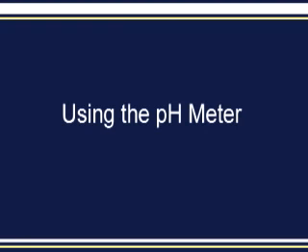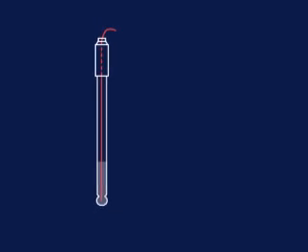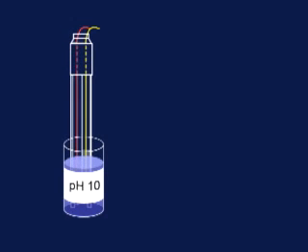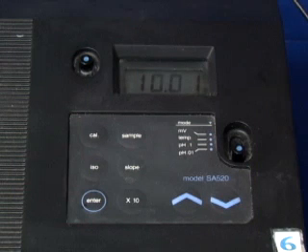For the second method of buffer preparation, you needed a pH meter. The final part of this video will discuss the proper use of this equipment. A pH meter allows the determination of hydrogen ion activity by a potentiometric measurement using a glass electrode coaxially joined to a silver-silver chloride reference electrode. When the probe is immersed in solution, the reference electrode makes contact with the sample, which completes the electrical contact between the reference electrode, sample, and pH electrode. If the unknown solution has a different pH from the solution in the probe, an electrical potential results, which is registered on the meter.